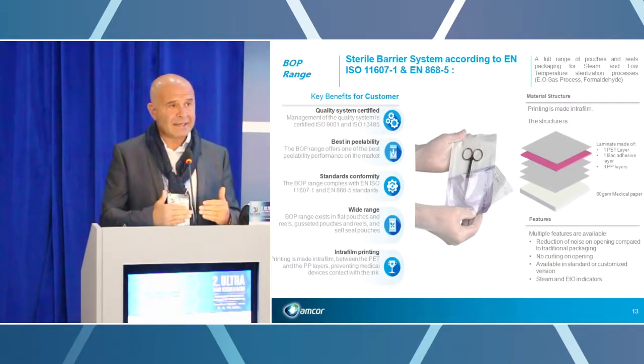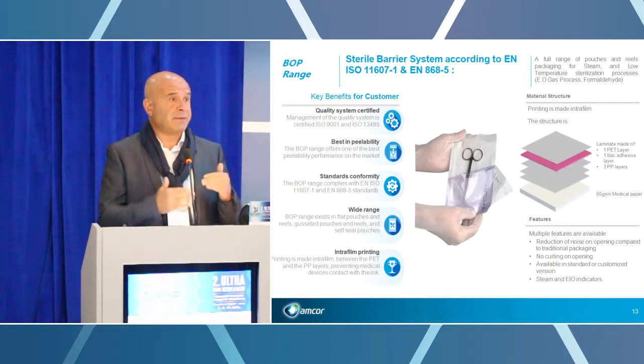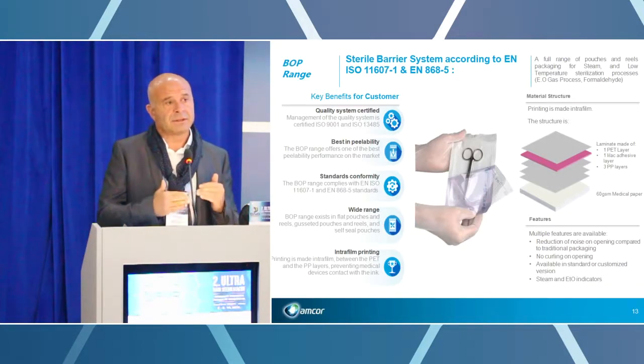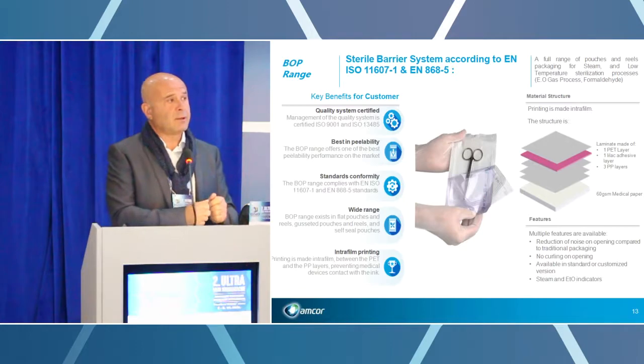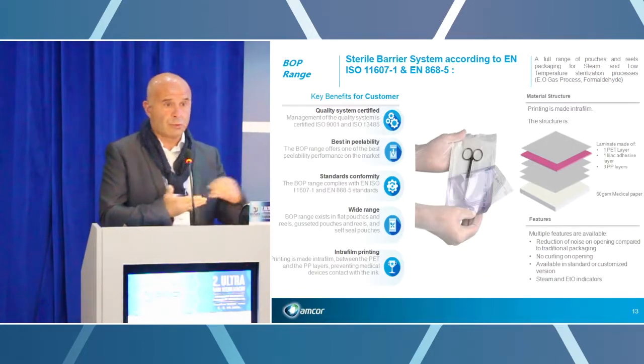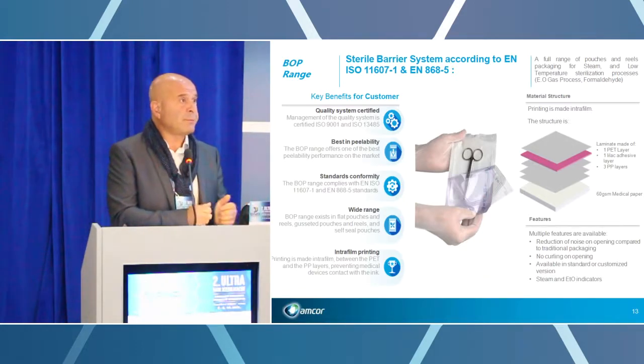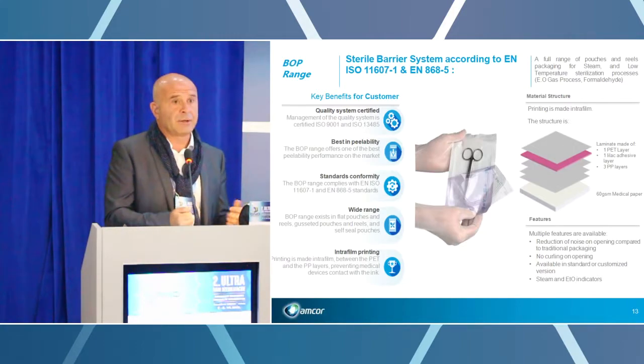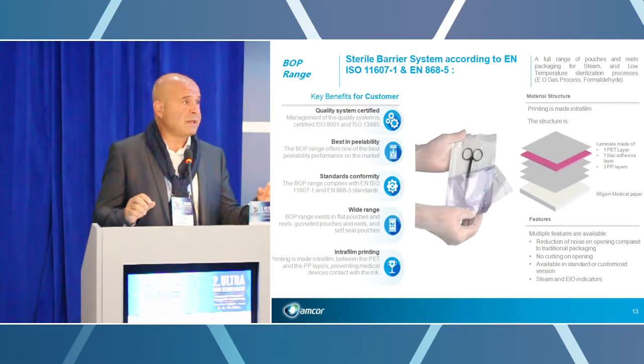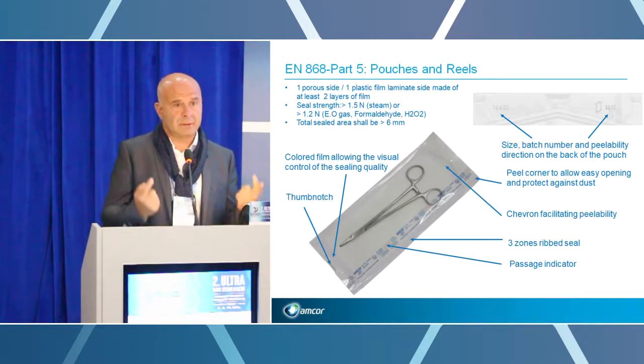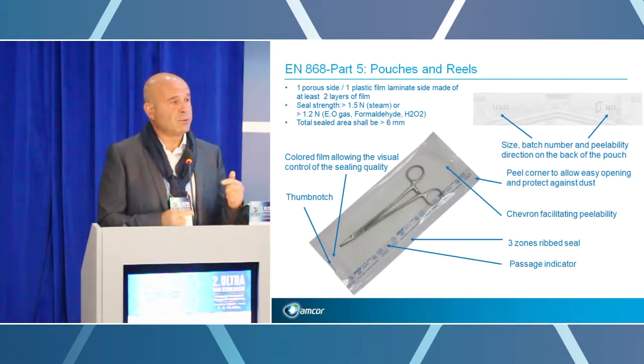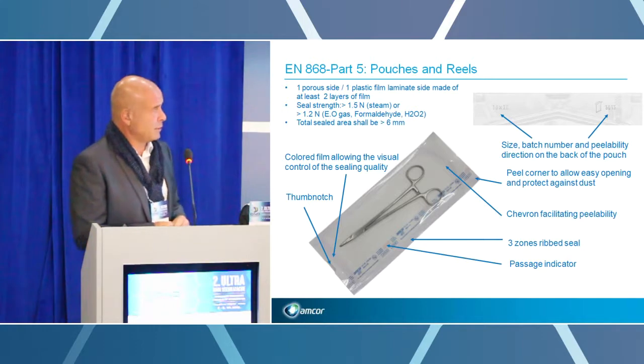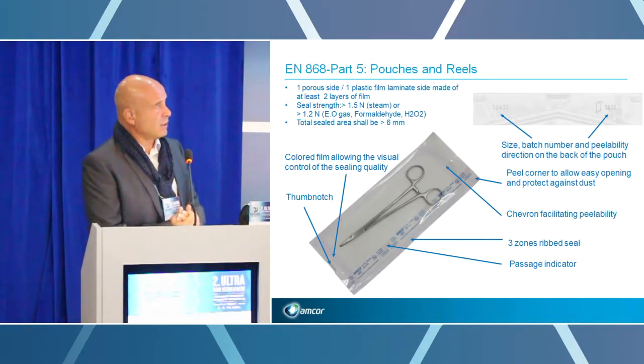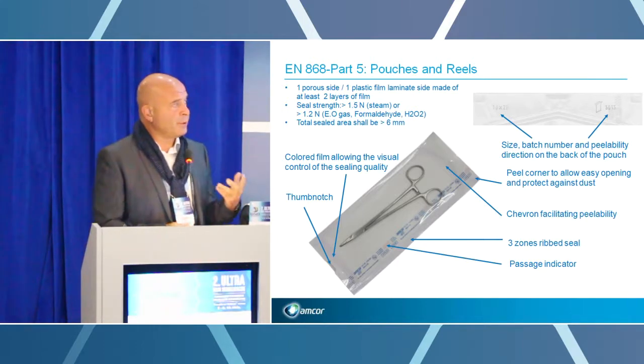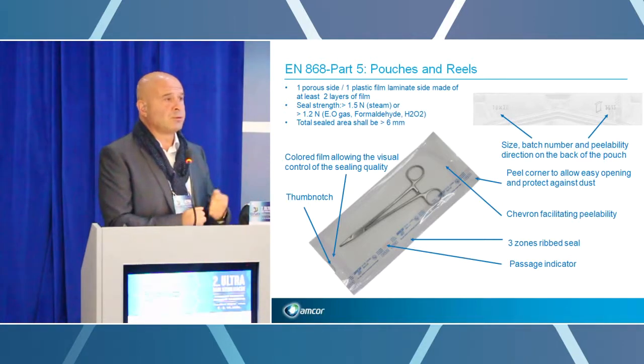With a seal, it's not the same, and it's very important you qualify your sealing machine, so that you have not just a strong seal, but a strong seal with the possibility to peel. Because if you have a very strong seal, it's not possible to peel. It's very important you do the qualification for the sealing machine. And you have a passage indicator and 3 zones ribbed seal. For our seal, it's just for the good peelability.